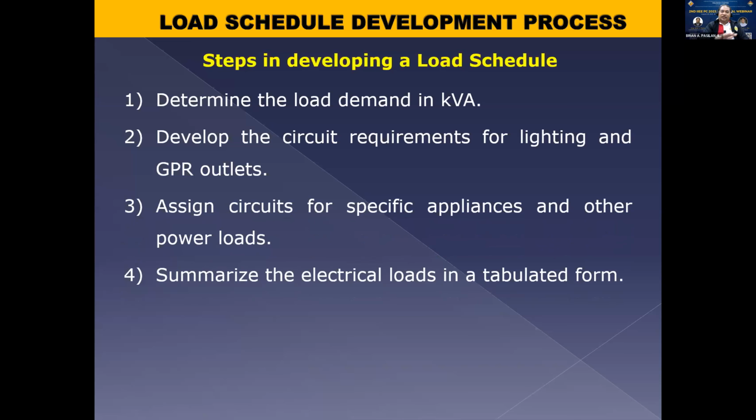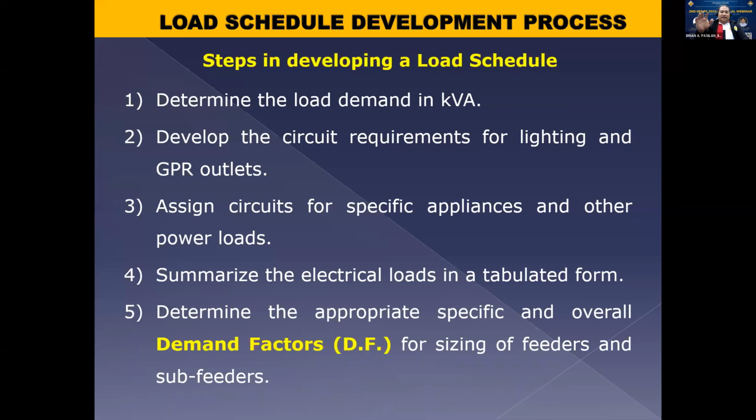Then after doing that circuit assignment, summarize all of this in a tabulated form. Ito na yung tinawag natin na load schedule. So, once we complete the load schedule, to size up the feeder conductors, we now need to determine the overall demand factor. So meron din tayong process niyan. Hindi yan parang out of the blue na factor, kasi ito rin yung practice ng mga bagong engineers natin, because of that virtue of copy paste.